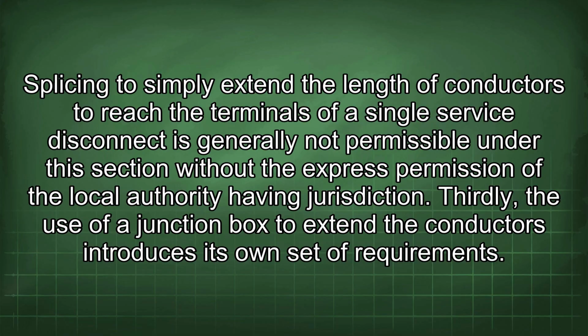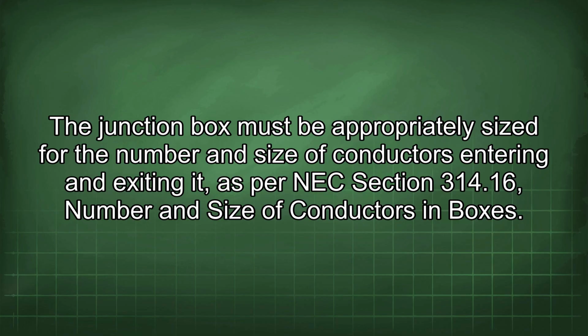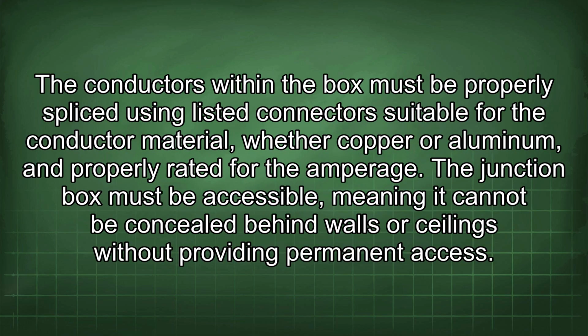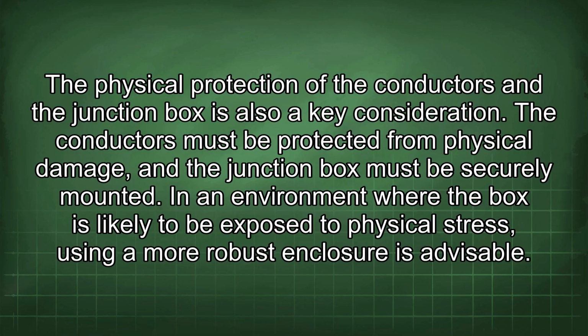Thirdly, the use of a junction box to extend the conductors introduces its own set of requirements. The junction box must be appropriately sized for the number and size of conductors entering and exiting it, as per NEC section 314.16, Number and Size of Conductors in Boxes. The conductors within the box must be properly spliced using listed connectors suitable for the conductor material, whether copper or aluminum, and properly rated for the amperage. The junction box must be accessible, meaning it cannot be concealed behind walls or ceilings without providing permanent access. The physical protection of the conductors and the junction box is also a key consideration. The conductors must be protected from physical damage, and the junction box must be securely mounted. In an environment where the box is likely to be exposed to physical stress, using a more robust enclosure is advisable.